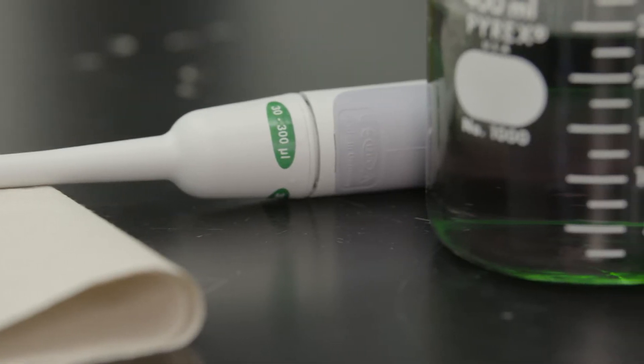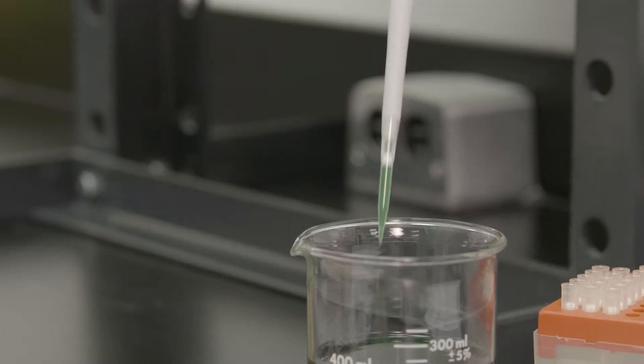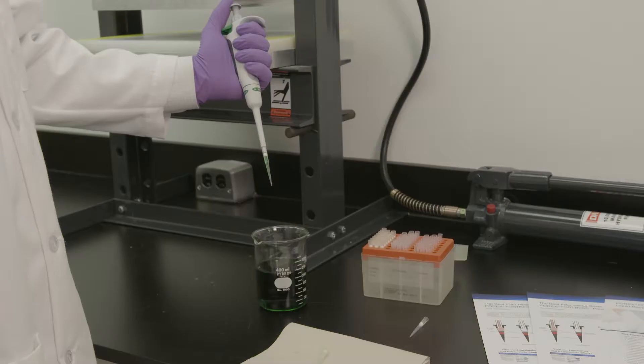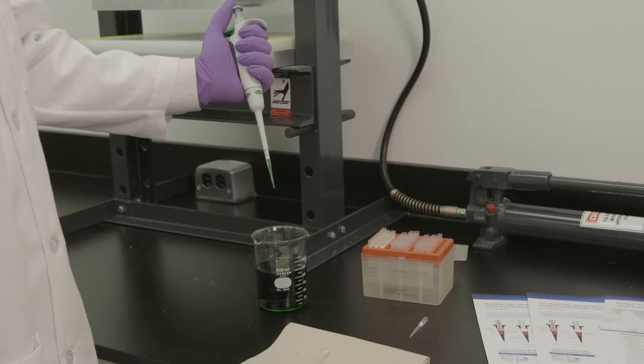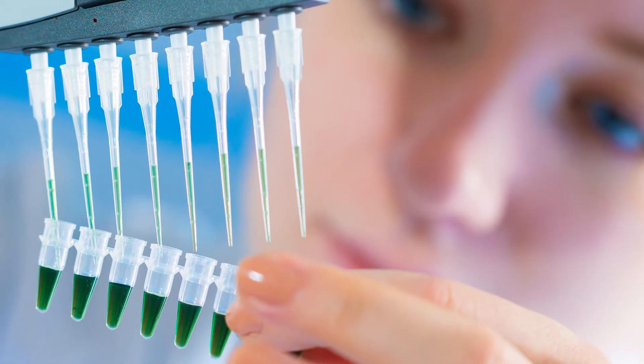Using green-colored water, all 200 UL filters, and a single-channel pipetter set at 300 UL draw volume, we will aspirate in an over-pipetting situation to demonstrate the effects of various filters under these circumstances.